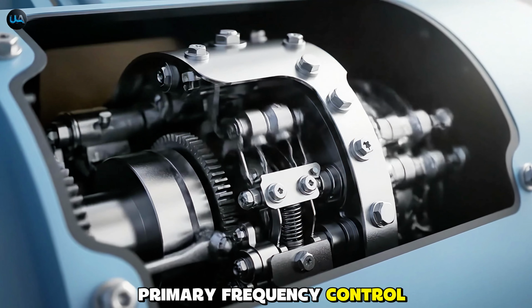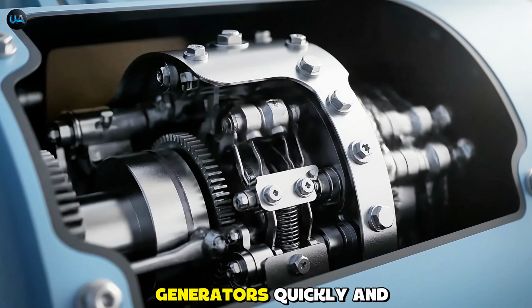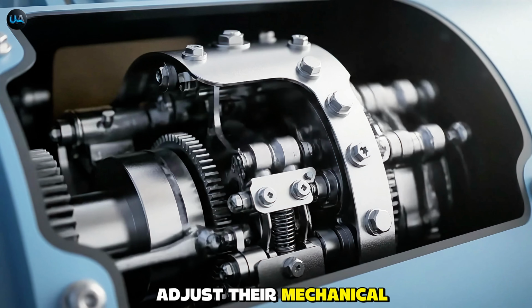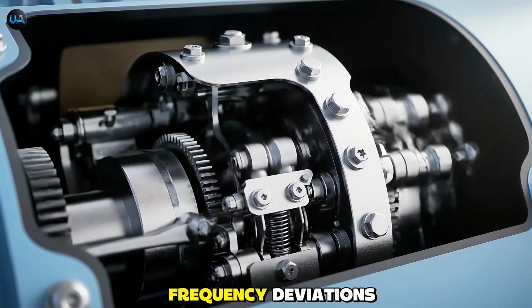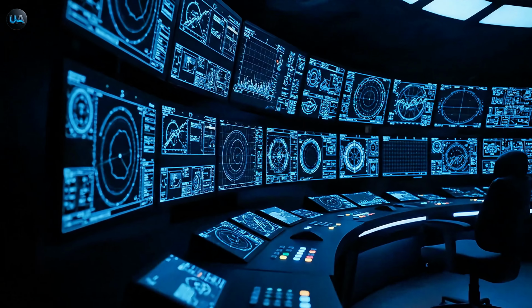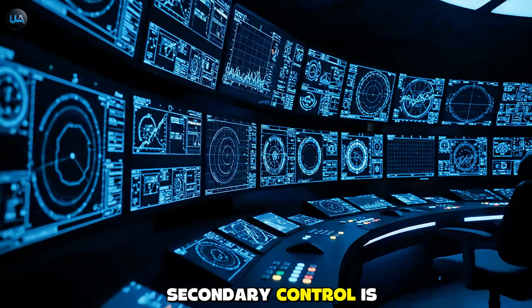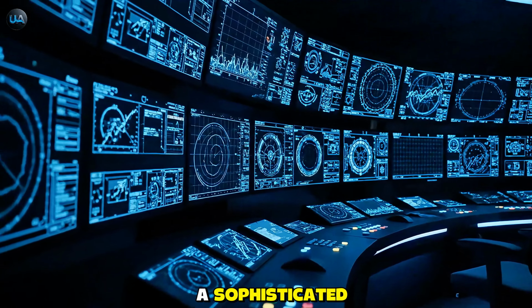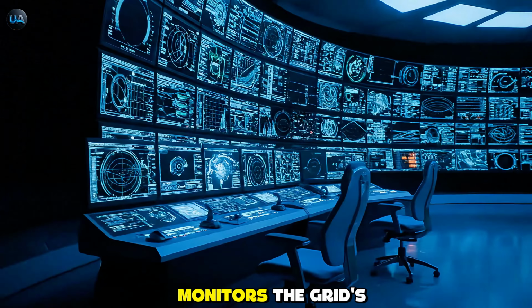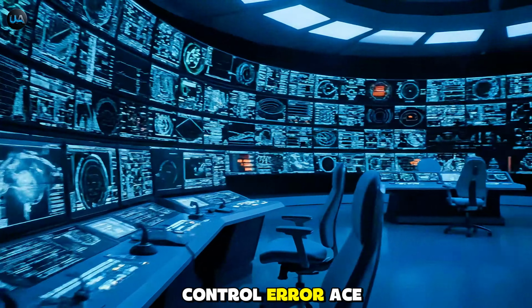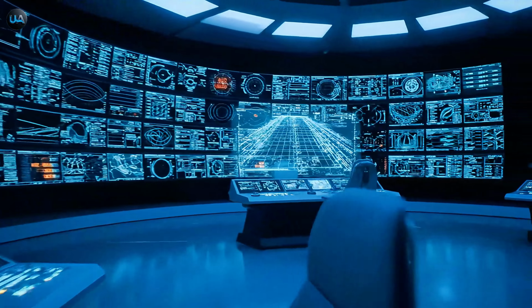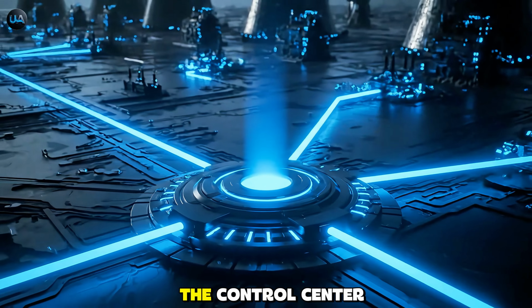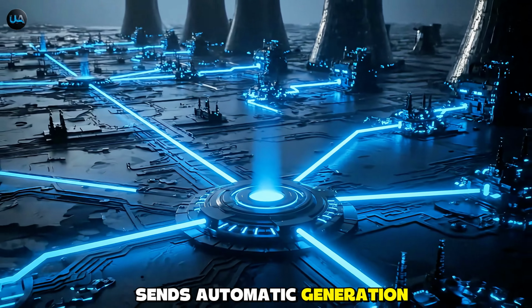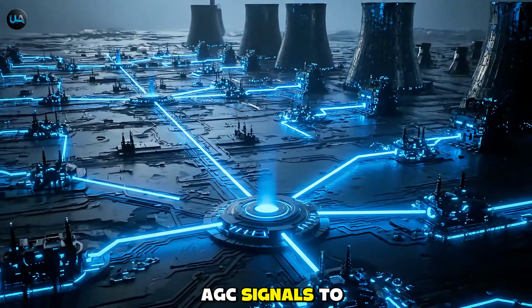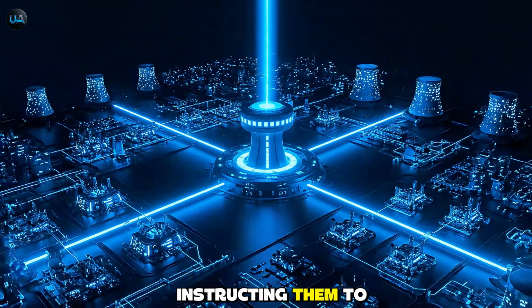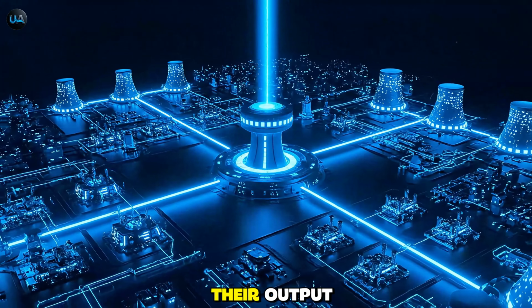Primary frequency control is instantaneous. Generators quickly and automatically adjust their mechanical input to correct minor frequency deviations. Secondary control is handled centrally. A sophisticated control center constantly monitors the grid's area control error (ACE). The control center sends automatic generation control (AGC) signals to power plants, instructing them to slowly ramp up or ramp down their output.